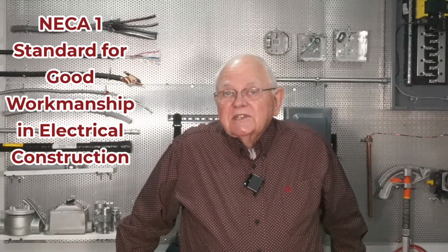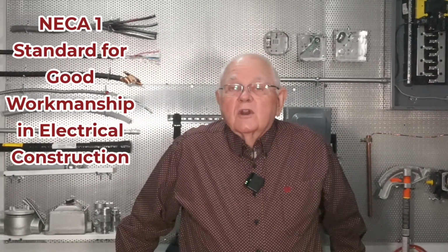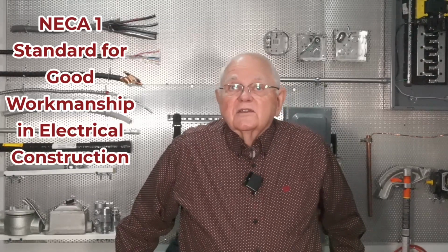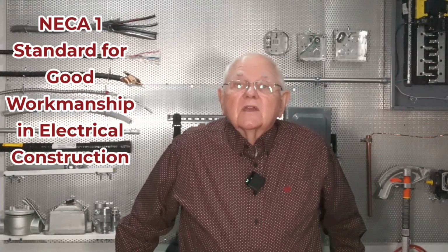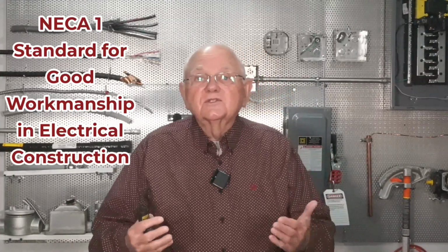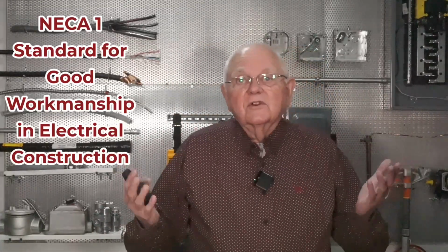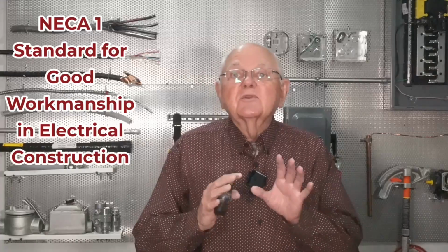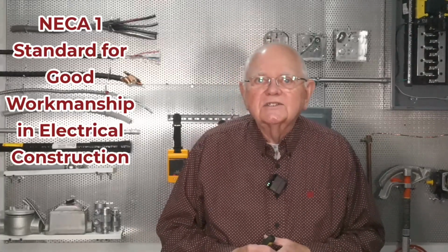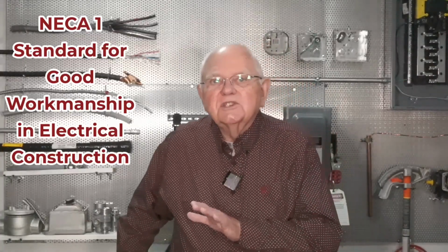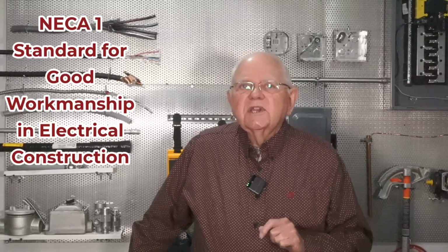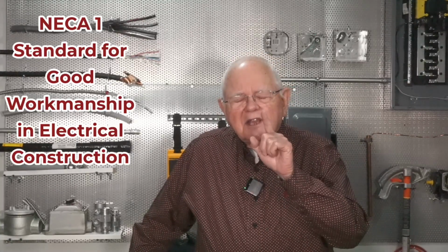The NECA 1 standard gets right up front and starts talking about you're on the job site and you get some electrical equipment, what are you going to do with it? So it talks about delivery, handling, and storage of my equipment. I should go ahead and inspect my equipment, it tells me, upon delivery. That makes sense. I handle it per the manufacturer's instructions and guidance. Store it in a clean, dry, ventilated area. It's interesting, it says rotate motors if needed. That kind of rung a bell with me.